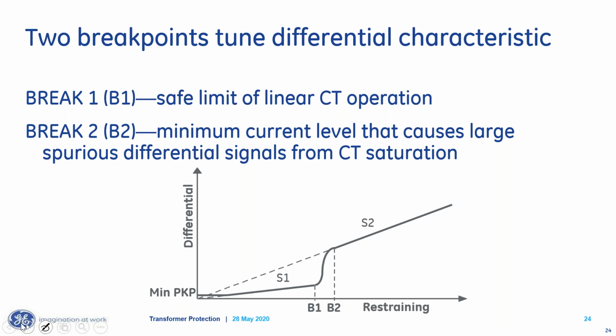I would recommend that nearly everybody sets this by a rule of thumb. For that upper slope, that is not a light fault once you get past that upper break point. If you're in that region, that's not a light fault, if it's a legitimate fault. So for that reason, you can set that upper slope extremely high. It should be set to somewhere around 80% in transformers. With other differentials, stator differentials, you can set that down to around 60%. Minimum pickup.